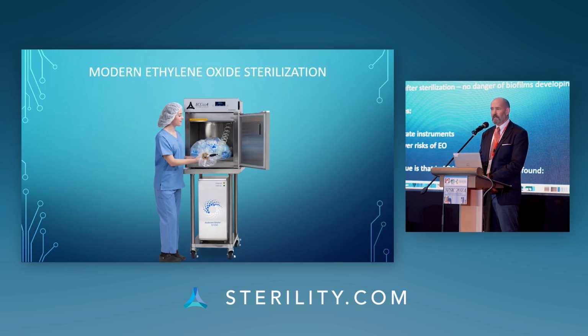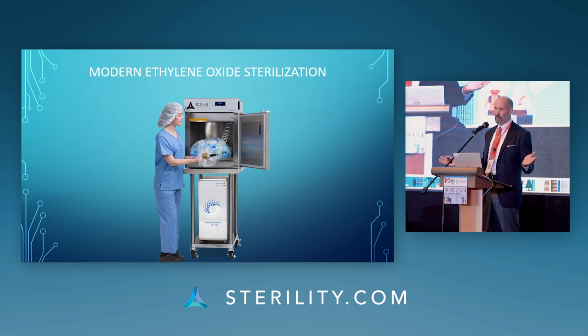I want to talk today about advances in ethylene oxide technology. One of the great misconceptions that we run into is the belief that ethylene oxide sterilization hasn't changed. And this simply is not true. Ethylene oxide has developed dramatically over the last 10 years. And the dramatic improvement has been in flexible chamber technology.